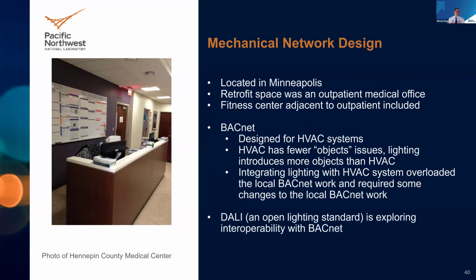Another challenge mentioned briefly in earlier presentations was BACnet. BACnet's pretty standard for a lot of mechanical systems - it's not the only communication protocol. However, mechanical systems have fewer objects - 'objects' being a technical term within BACnet. As a result, when this project introduced all the light fixtures and sensors into the BACnet network on site, they crashed the network because it wasn't designed to handle that many elements.